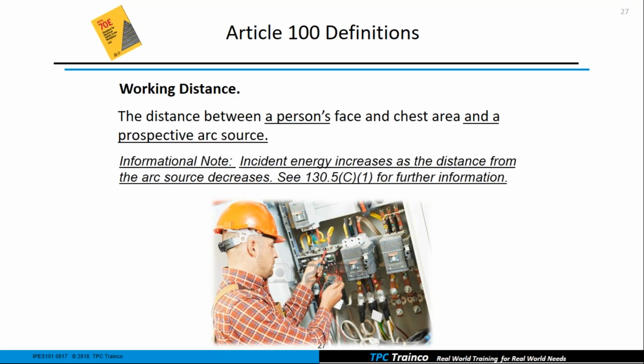I don't think personally at my age that I can work 18 inches away from equipment. I believe I've got to get a little bit closer. So they gave us this note that said that incident energy increases as the distance from the arc source decreases. So when I get closer, that 7 calories has gone up, and I've got to make sure that my arc-rated clothing will reflect that as I get closer. Definitely my eyes have probably got to get closer, and my hands have to get closer. But they're talking about your face and your chest. If you can keep that 18 inches away, then you would be at that incident energy level that we did predict at that piece of equipment.